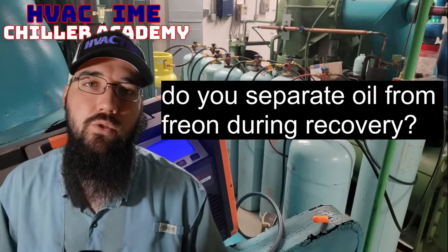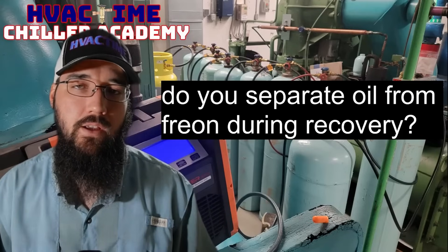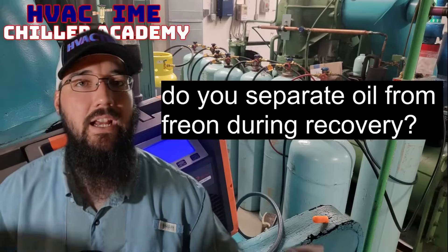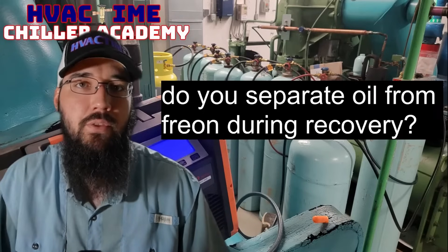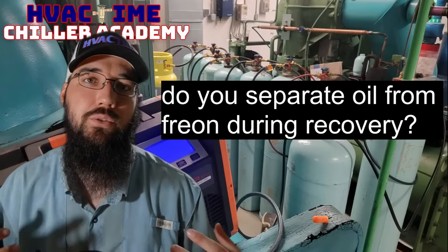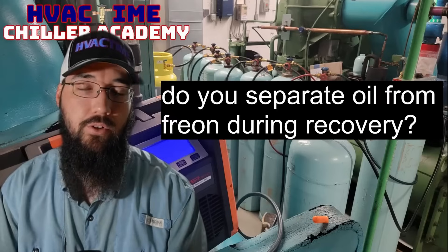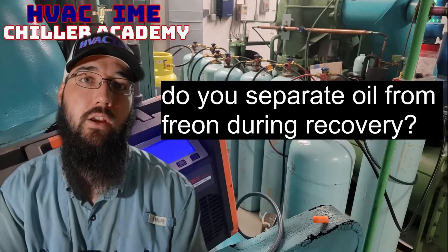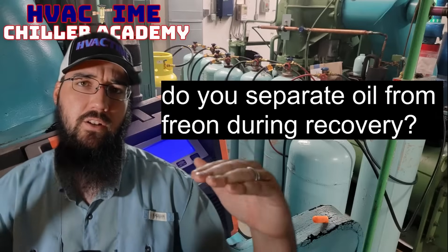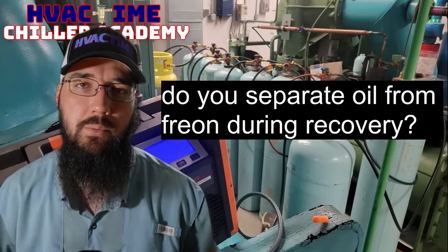We can't directly separate them during the recovery phase. If we have a machine that had heavy oil migration or oil stacked in the evaporator — which is a fairly common thing we have to deal with — and the refrigerant you took out was very oil-laden, you go through the full recovery. All of that oil is going to mix with the refrigerant, and that oil is going to settle at the top of the refrigerant level.